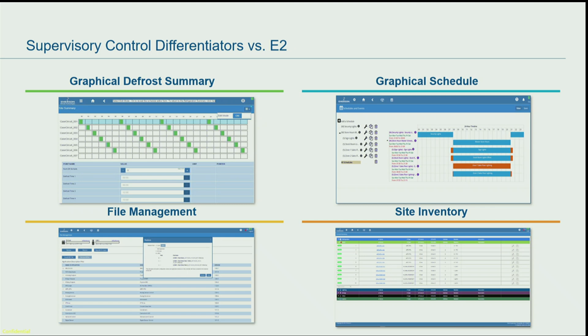We talked a little bit about alarms and how you can build your own. What we've added is a new feature called smart alarms. Some of these are pre-built, and some you can customize yourself. We have user-defined messages where you can add an explanation of what causes them, possible causes, maybe what makes it fail, and suggested action - go check this transducer, go check this filter sensor, maybe label where the power is, what makes it or breaks it down. It'll tell you when the alarm was created, what type it is, whether it's critical or non-critical, the time it occurred, how old it is, and what unit it's tied to. If you've got multiple units, it'll tell me which unit controller is affected.